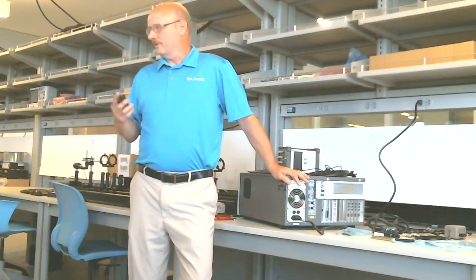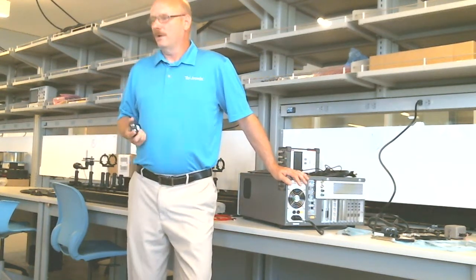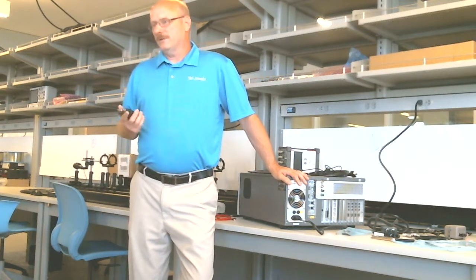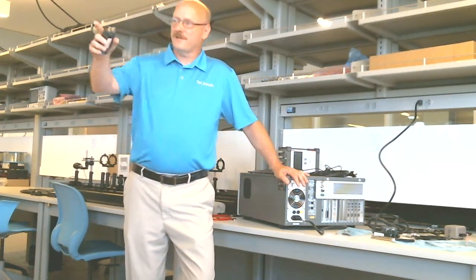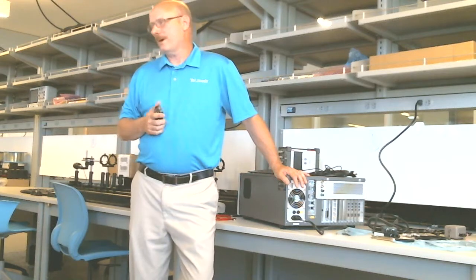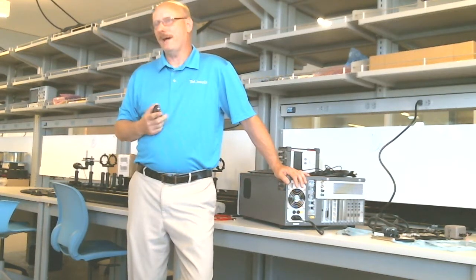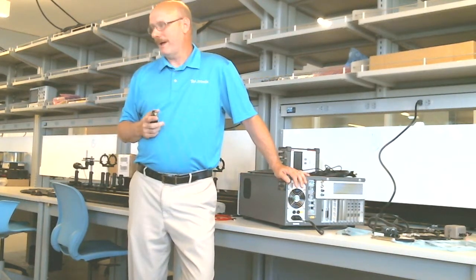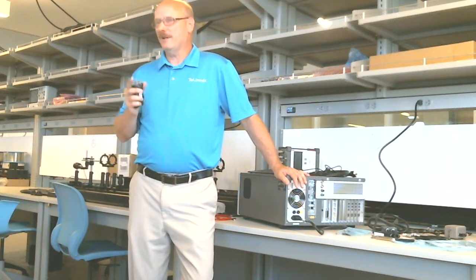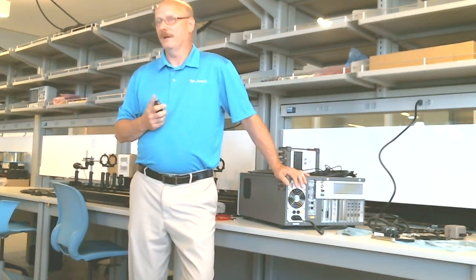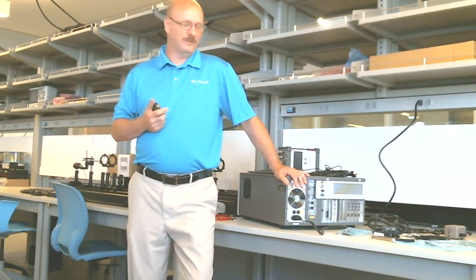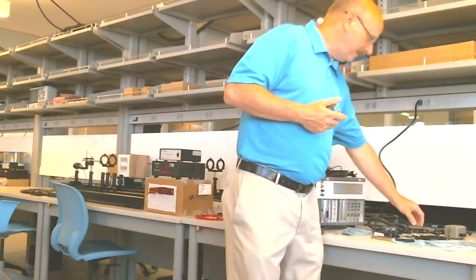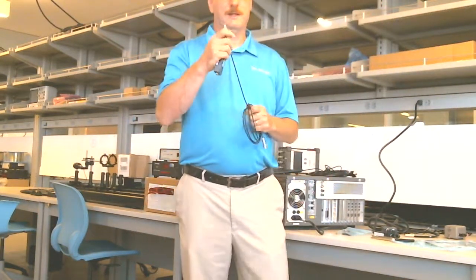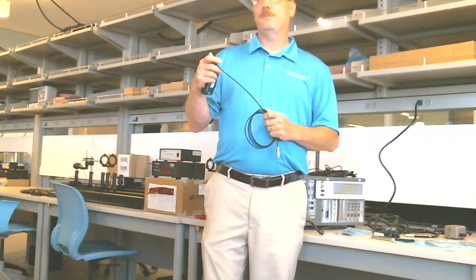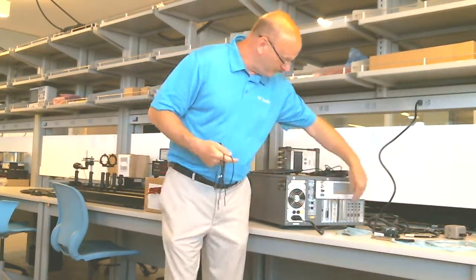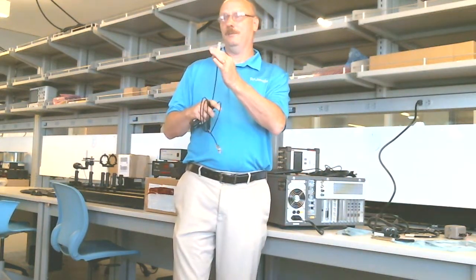So your service is local. What I'd suggest is, hang on to those boxes you've got over there, because if you want to send it back for calibration, you'll want to pack it nicely, and send everything with it. We calibrate to the end of the cable, which most people don't do, they calibrate to the output of the instrument. We calibrate to the end of the cable.